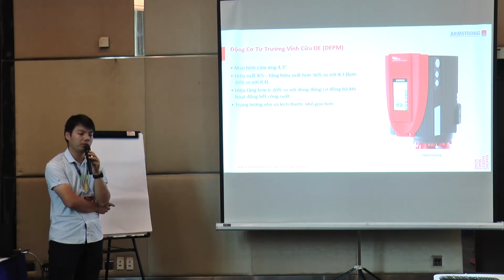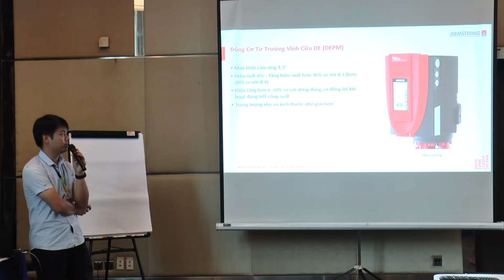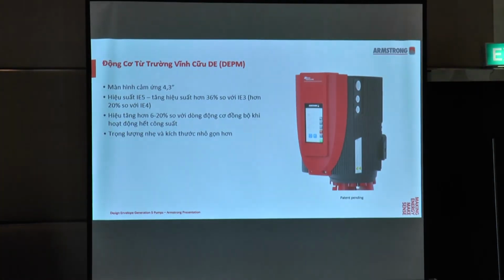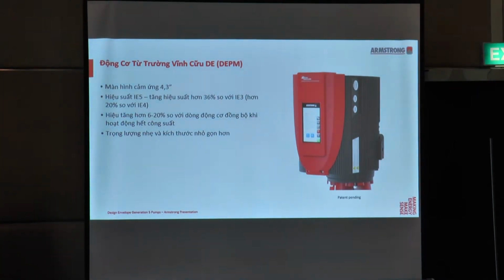Okay, now let's look at the newest DEPM motors. We mean the design envelope permanent magnetic motors. So this motor has the 4.3-inch colorful touch screen. And for the efficiency, it can meet the European IE5 standards. And this would have about 36% higher than the IE3.